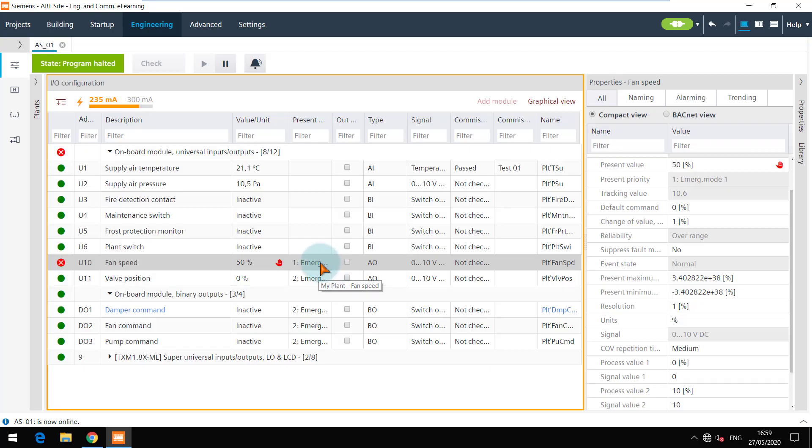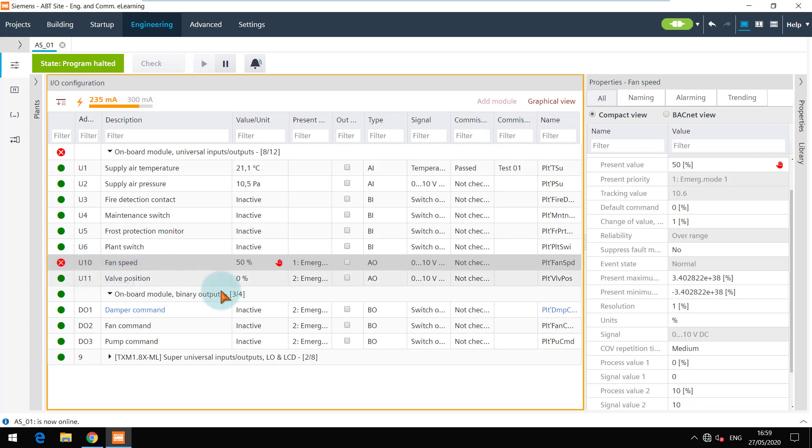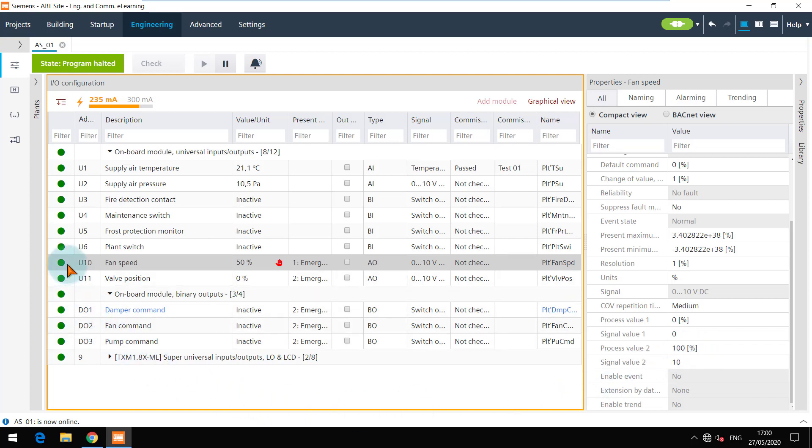The data point has an error and the reliability is over range. Yes, since the process value 2 is 10, the value given by us exceeds it. As per my simulation, I will change this value to 100. And now the error is resolved and I can see the correct output.